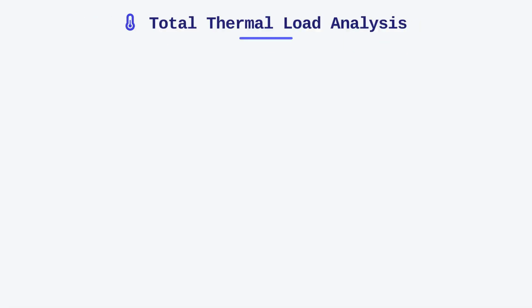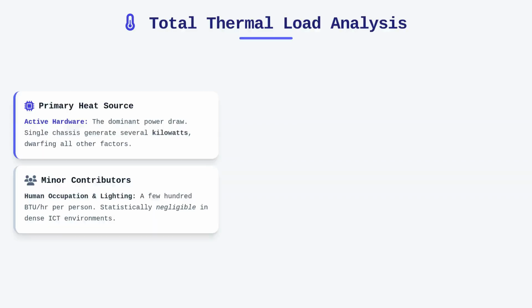Human occupation and lighting also contribute to the total heat load, though in a modern, highly dense ICT environment, these values are often negligible compared to the massive power draw of the active hardware. When we account for personnel, we typically estimate a sensible heat gain of a few hundred BTU per hour per occupant, which is statistically insignificant when compared to a single chassis generating several kilowatts.